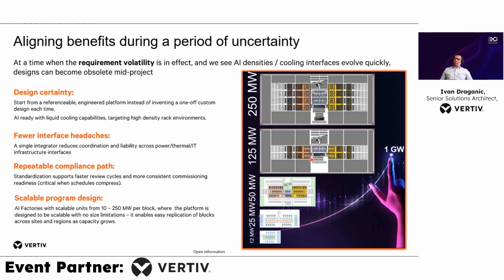So how do we build it with a traditional approach? We do repeatable block design. Looking at the image on the right, the top picture is a 250 megawatt AI GPU-filled data center featuring several data halls, with 4 distinct halls on the right side and 4 on the left. In the middle is a core networking section, a prerequisite for such a big data center, where all the networking combines and gets routed to go outside. The 125 megawatt reference design is basically half of what we had above, so for the big one we've just copy-pasted this, and as we go lower we get into more repeatable blocks. Next I'll show you how exactly one of these blocks is built and what it consists of.